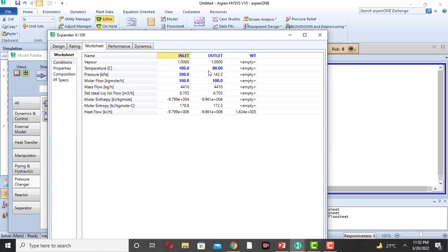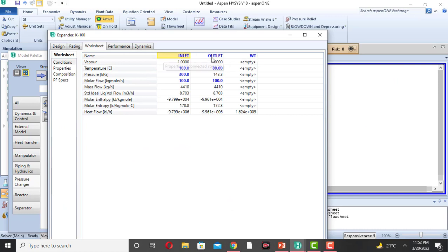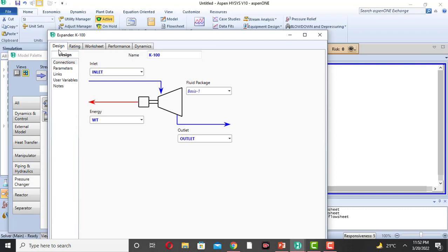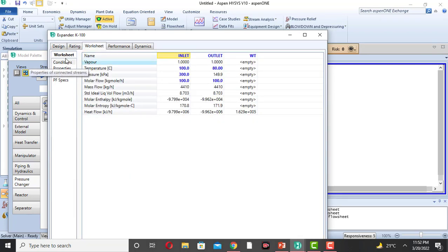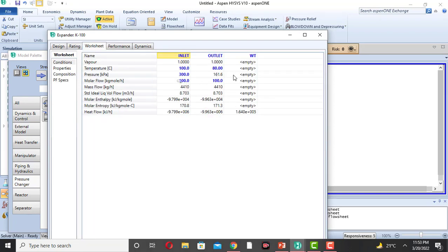Now come to the worksheet. The unknown quantity is the outlet pressure. This is inlet, this is outlet, and this is the work of the turbine. The outlet pressure is 143 kilopascal. In the design parameters, the efficiency of the turbine is 75%. If we change the efficiency to 80%, the outlet pressure becomes 149 kPa. If the efficiency is 90%, the outlet pressure becomes 161 kPa. So the outlet pressure increases as we increase the efficiency of the turbine.